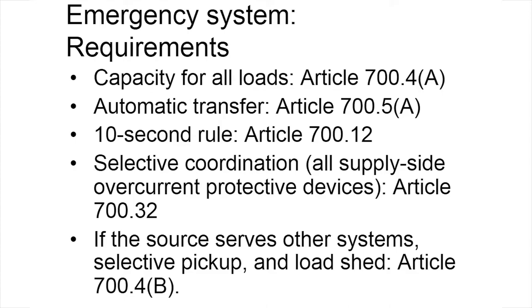Here are some of the requirements for emergency systems. This list covers some of the more interesting requirements. The capacity of the emergency system has to be enough to operate all the loads connected to the system simultaneously. This is a very stringent requirement. It's unlikely that the system will ever have to serve everything that's connected to it at 100% load at the same time. But the nature of an emergency system just demands that it be prepared for whatever is asked of it, so we have this requirement.